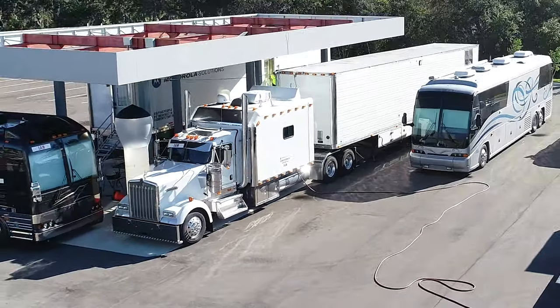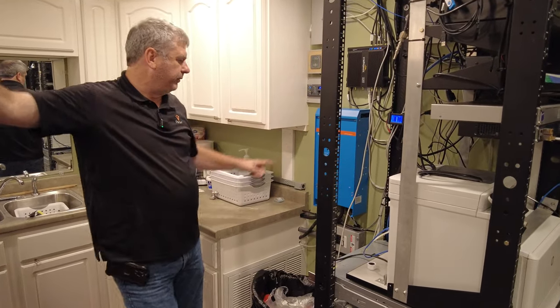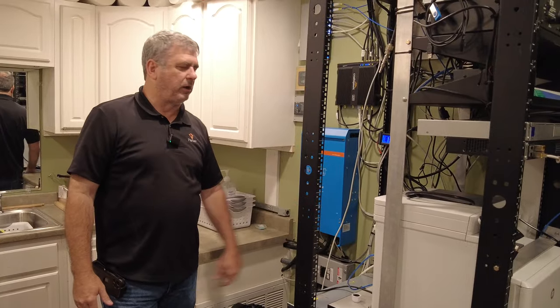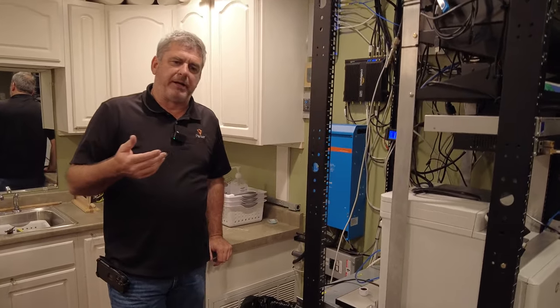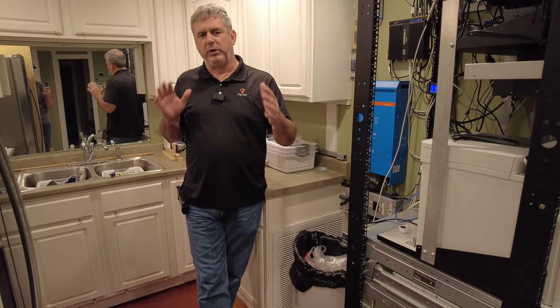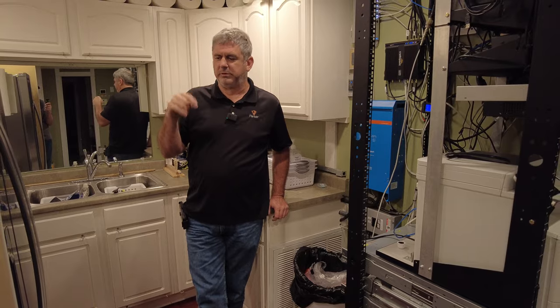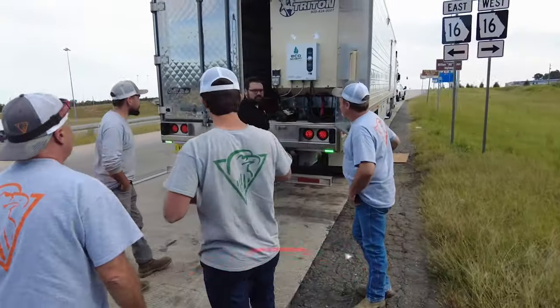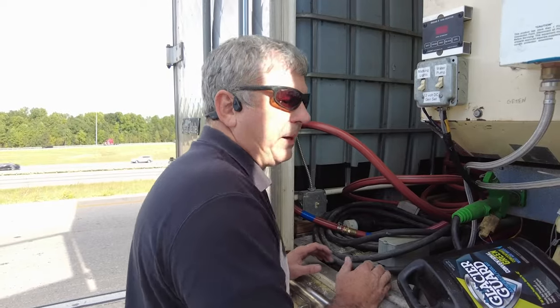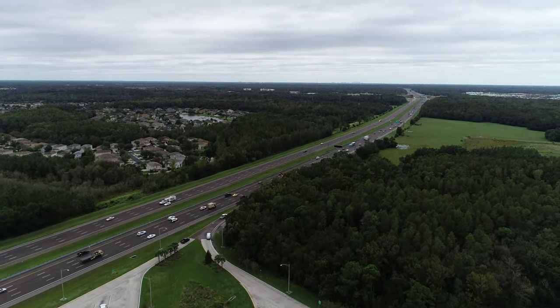This is the original sleeping trailer and right here we have our inverter. This one's a little different than the one in Sleeping Trailer 2. We've got a 2,000-watt inverter by Victron, and we've increased our battery bank to 600 amp-hours of storage. With a lot of server equipment and a lot of gear drawing 750 to 1,000 watts, we need a lot of backup power. This trailer also has a full-size refrigerator and a deep freeze, so our power requirements give us up to 12 to 14 hours of runtime. There's a big 80 kVA, 60 kW generator in the back of this trailer. We've never had a problem in 14 years of deployment until the last one, so we upgraded our battery size. It's important to have redundant systems — in case we lose the generator, we've got the Victron system with the Battle Born batteries to give us 10 to 14 hours of confirmed runtime.